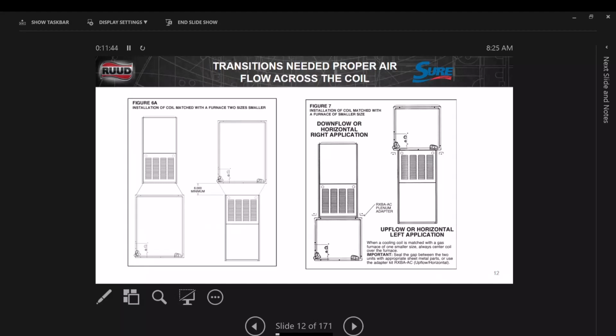Now, if you've been to some of my furnace classes, you've heard me talk about this before, but we're talking about matching that coil to that furnace. When we go and do something like this, it is okay. But if we are 2 sizes larger than the furnace, we're going to require a transition. And that's nothing new. It's been in our installation manual for a long time.